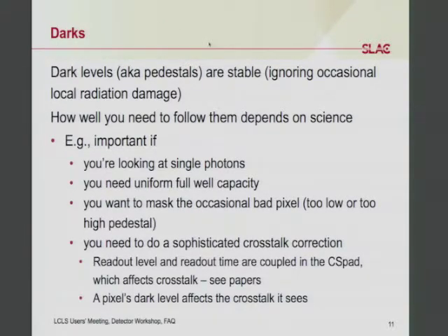So some comments about the darks. They're stable, but if you really want to get the best single photon counting you can, then it's a good idea to update your darks more frequently than you would otherwise. If you're in a high radiation environment and you care about knowing the exact behavior of every single pixel, then it's important.